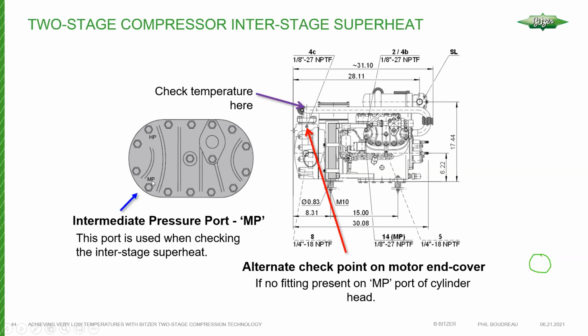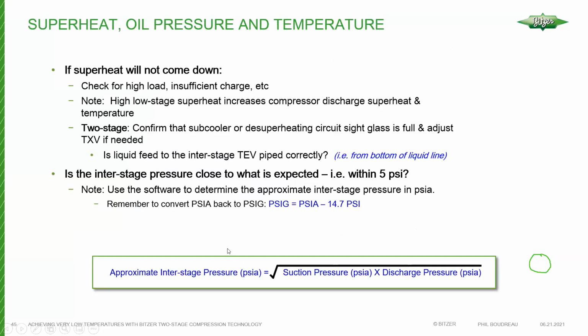You'll see a port marked MP. Let's call it medium pressure. So on the low stage heads, you'll see LP and MP. On the high stage head, you'll see an MP and an HP. Okay, and there is something that we can check. There are some notes in here about if superheat won't come down. If it can't come down, you could be low on charge, maybe we have a flow issue on the interstage side, or there are a number of things that can happen. Valve starvation, the whole bit.